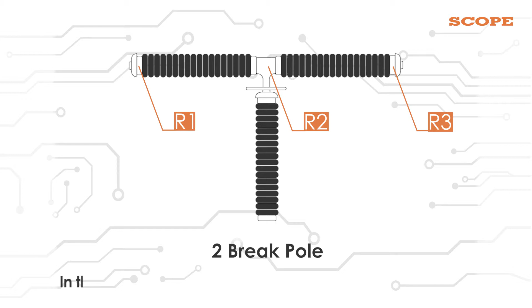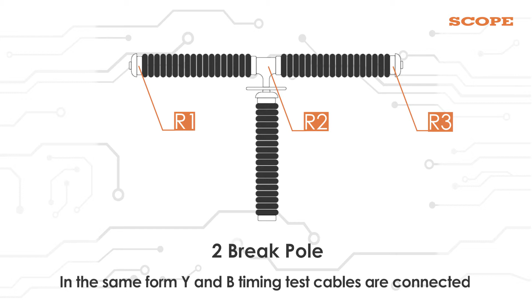In case of single break per pole, R1 and R common are connected to the circuit breaker, while R2 should not be kept floating. It is connected to the porcelain. And for 2 break per pole, R1, R2 and R3 are connected to the circuit breaker. In the same form, Y and B timing test cables are connected. Now, as we are done with the connections, we will start the test.